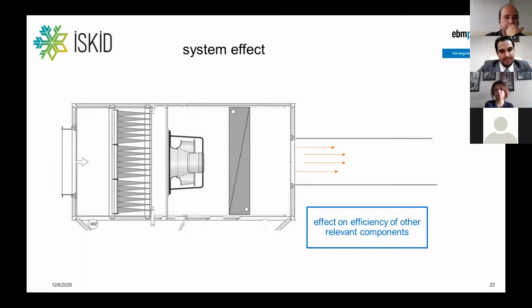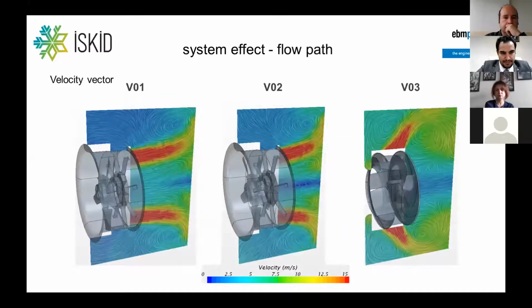Another point is the interaction of the fan flow and, for example, a coil or a filter, which is located downstream of the fan. So the system effect is not only pressure losses due to the flow, it's also the efficiency of the components inside the unit. So if you have a very well distributed airflow through a coil, the coil performance will increase. The exchange rate will increase.